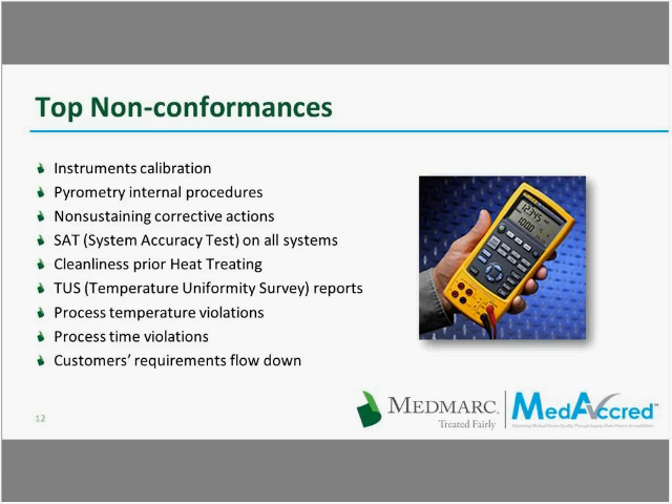We have a broader program called NADCAP in the aerospace industry. MedAccred has only one or two years of history, but PRI has over 25 years in the similar NADCAP program. We have seen many non-conformances over those 25 years, and they were summarized here. Looking at the top non-conformances in heat treating audits, pyrometry was the main culprit — instruments calibration and pyrometry internal procedures that flowed down requirements to operators.